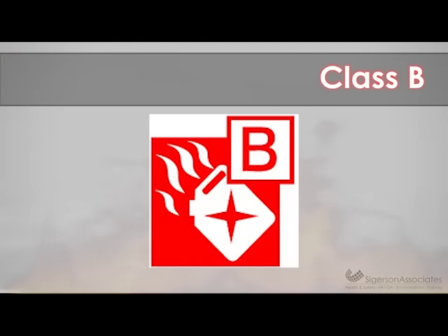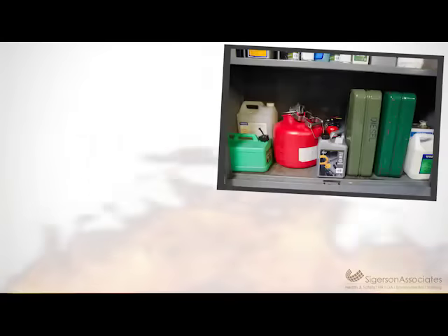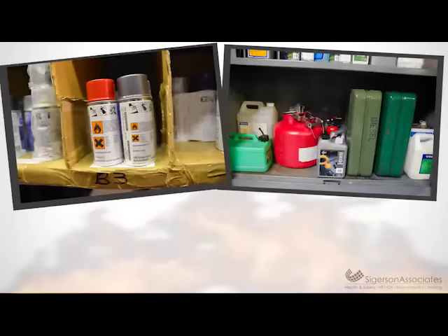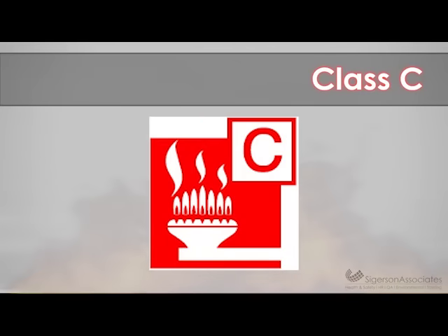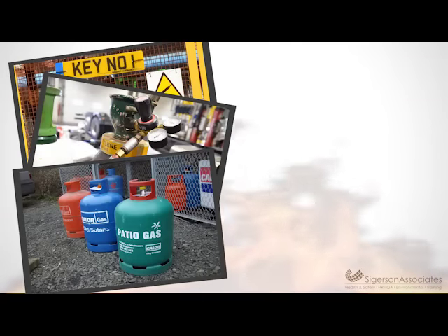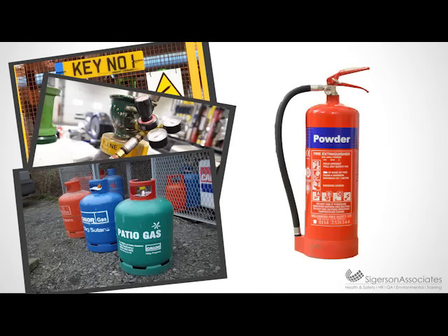Class B. These fires involve flammable liquids such as petrol, diesel, thinners and paints. These types of fire can be tackled using foam, dry powder or CO2 extinguishers. Class C. Fires involving flammable gases such as acetylene, propane, butane and methane. These can be tackled using dry powder extinguishers.